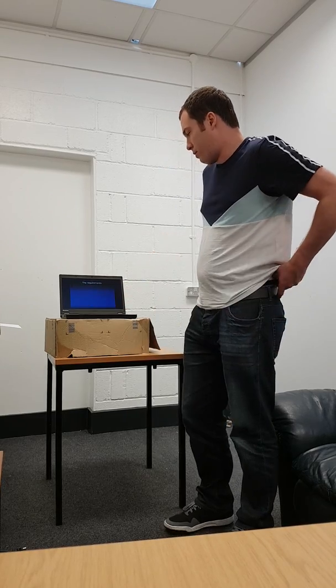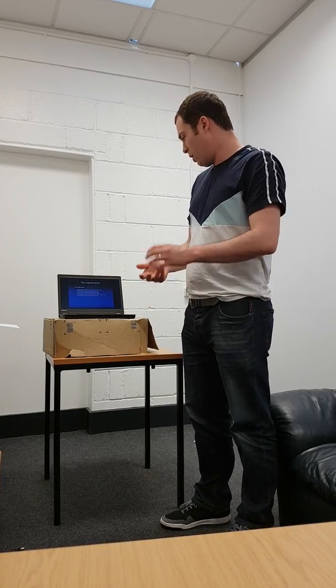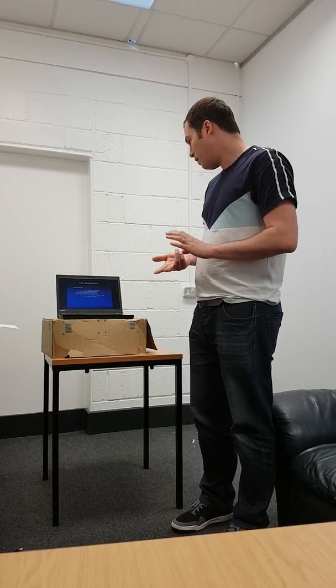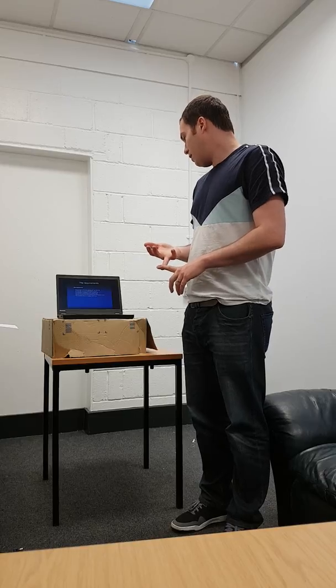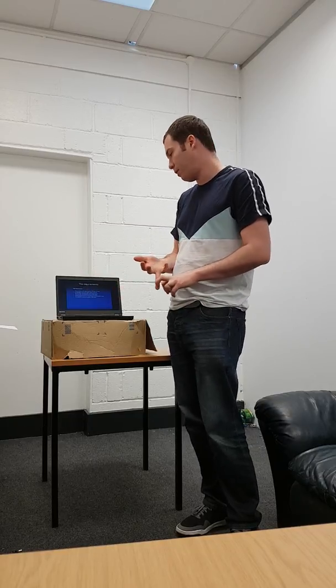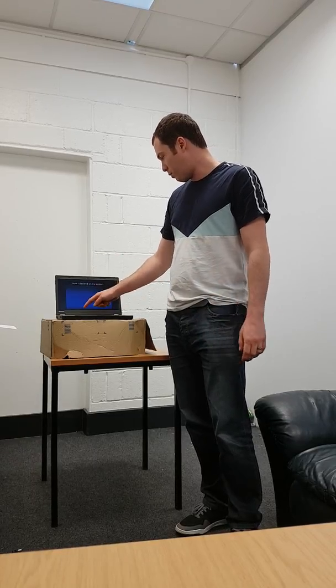So the main requirements which we came up with were things like: it had to fit in a 19-inch rack, because we use 19-inch racks everywhere. You have to be able to manually control the chiller with an on-off switch, just for fail-safe purposes. Obviously, there's the temperature of the water. Then a safety trip, so if anything does fail, like temperature too high or flow fails, it trips off and the power supply is in safe mode. And we want all of that controlled off a single 13-amp socket just to make it easy. So those are the main requirements.